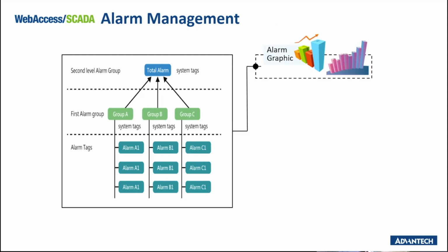First, we go into the alarm graphic. The alarm graphic is configurable for each tag in the system. From the alarm summary display, the operator can call up this alarm graphic with a single mouse click. The alarm graphic can be any graphical display in the system. Typically, it's a process graphic giving the operator the most information on the cause or solution of the alarm condition.